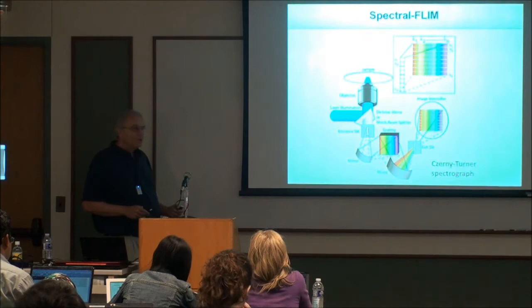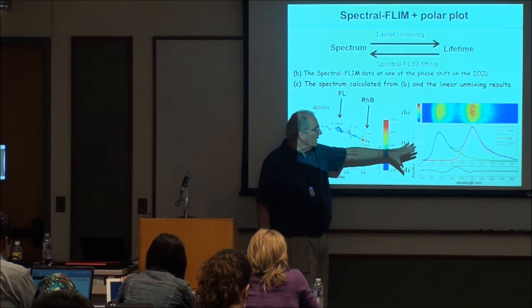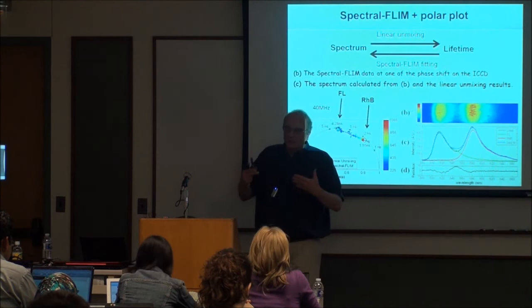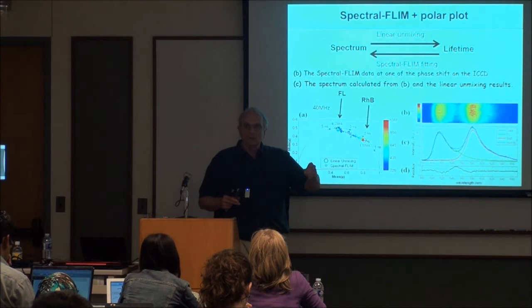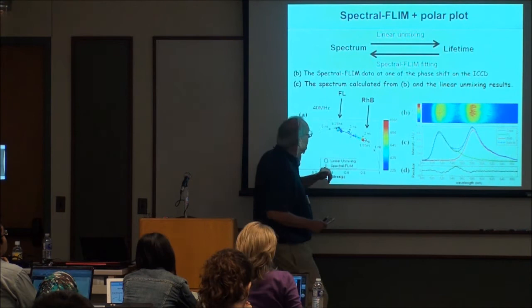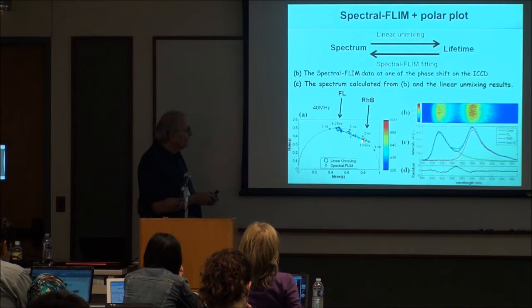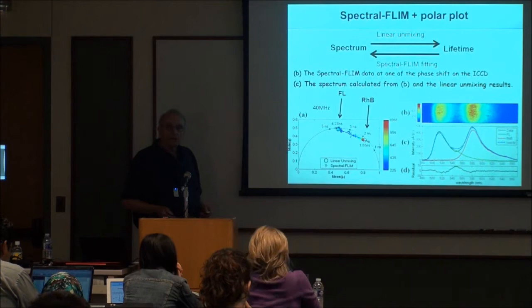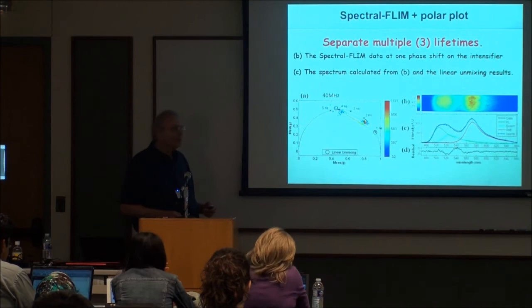One more thing: spectral FLIM. You can couple this with spectra — so if I have fluorescein and rhodamine in solution, I take a spectrum and lifetime data at the same time. At every pixel of my picture, I'm getting spectral information and lifetime information simultaneously. Here we have fluorescein, here we have rhodamine, and in between they're mixed. I can combine the lifetimes in the image with the spectra and use that information — I can even analyze three dyes in certain situations.